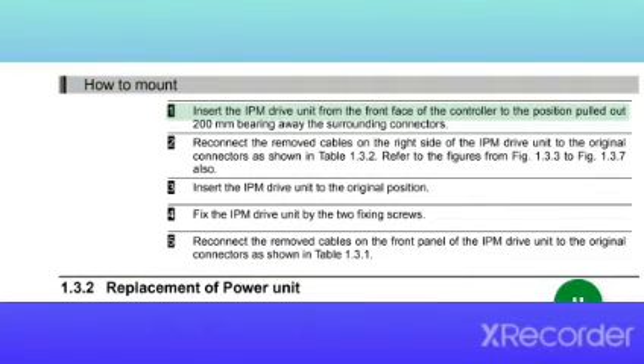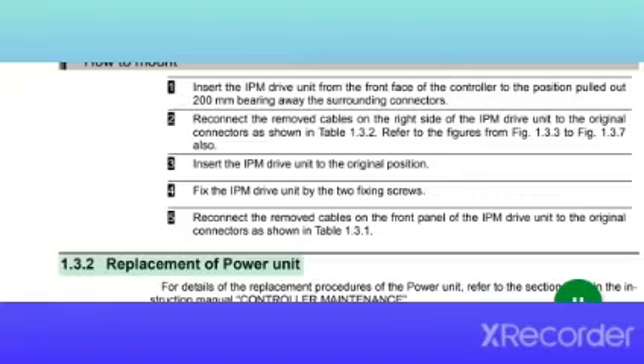How to mount. 1. Insert the IPM Drive Unit from the front face of the controller to the position pulled out, 200 mm, keeping away from the surrounding connectors. 2. Reconnect the removed cables on the right side of the IPM Drive Unit to the original connectors as shown in Table 1.3.2. Refer to the figures from Fig. 1.3.3 to Fig. 1.3.7 also. 3. Insert the IPM Drive Unit to the original position. 4. Fix the IPM Drive Unit with the 2 fixing screws. 5. Reconnect the removed cables on the front panel of the IPM Drive Unit to the original connectors as shown in Table 1.3.1.